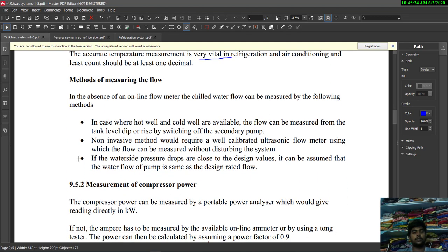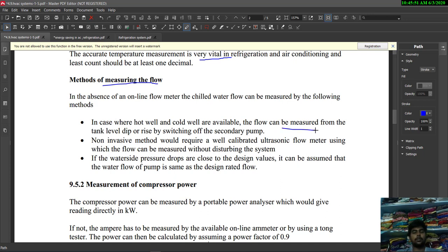The next topic is methods of measuring flow. In the absence of an online flow meter, the chilled water flow can be measured by the following methods: where hot well and cold well are available, the flow can be measured from the tank level rise or drop by switching off the secondary pump. The second method is a non-invasive method.